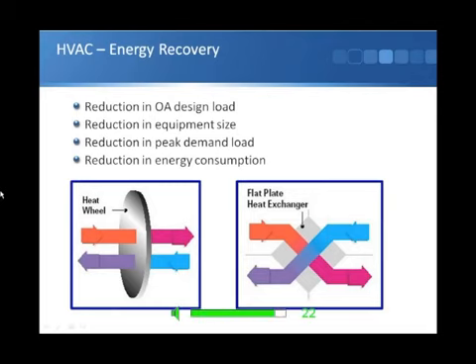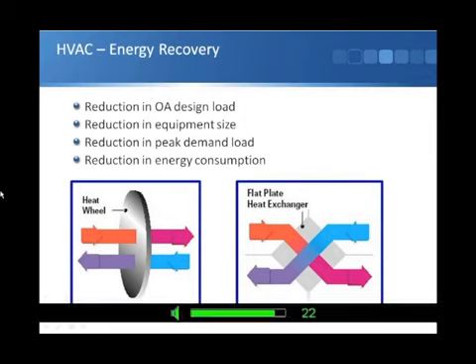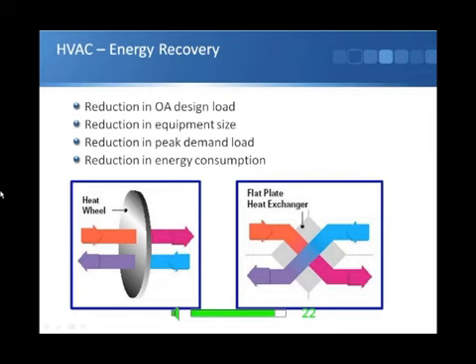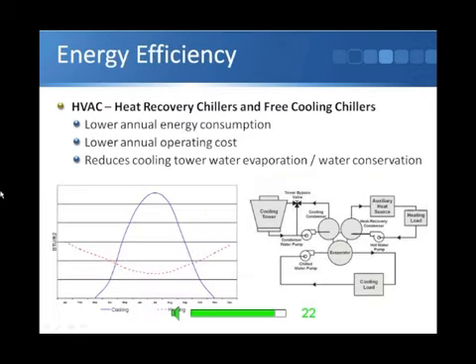When we're looking at ventilation systems, we really need to have a look very carefully at how we might recover heat and cooling. In the summer, of course, that heat goes out. The heat coming in the building can be cooled by the cooled air conditioned air going out, so we're able to recover energy there. And in the winter, of course, the other way around, we want to pick up waste heat that's going out so that we're preheating the air before we get to our heater battery. And that can reduce energy loads and demand significantly. And of course, better introduction of heat recovery chillers and even free cooling chillers.